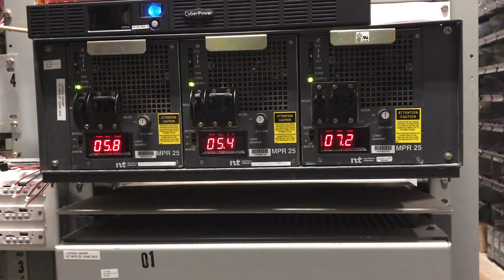Then from the batteries or the rectifier, wherever the power is spliced together — generally at a bus bar — there are feeds from the bus bar to high amp circuit breakers or fuses that distribute the load to what's referred to as a BDFB, a battery fuse distribution board.